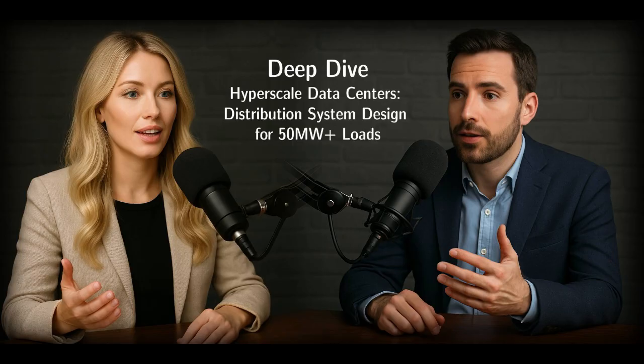It really does. You're essentially trying to handle a small transmission level load using distribution infrastructure, and the physics just starts working against you. Which brings us, I guess, to the core engineering decision here. Yes. Voltage level selection. Get this one decision wrong up front, and every single thing you do after that becomes harder, more expensive, and more complicated. It's absolutely critical. Okay, let's walk through the options, starting with the familiar territory, 12.47 kilovolt systems. Traditionally used for loads up to, say, 15 megawatts. Does that ever still work for data centers, and where does it break down?